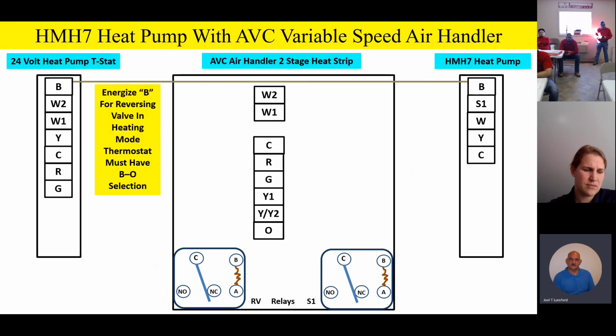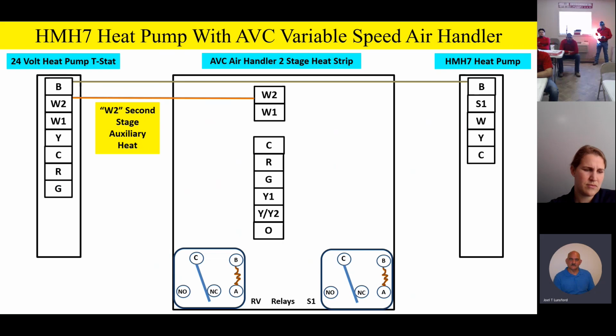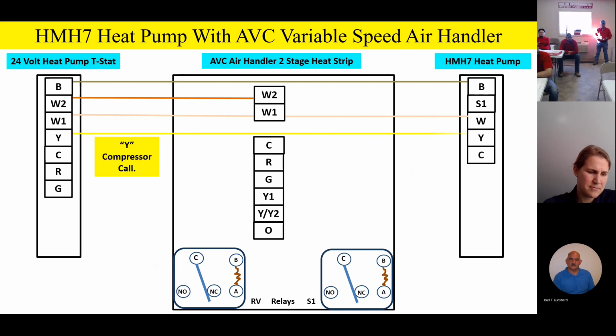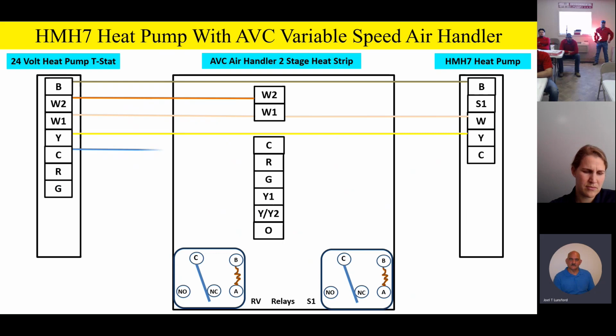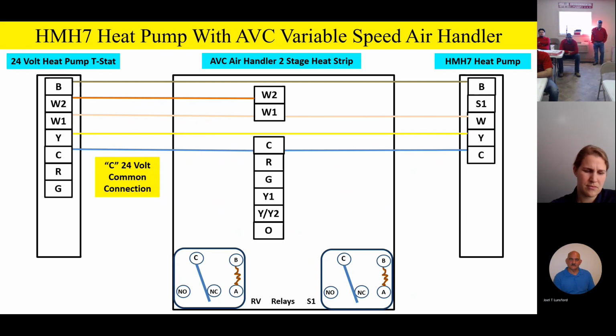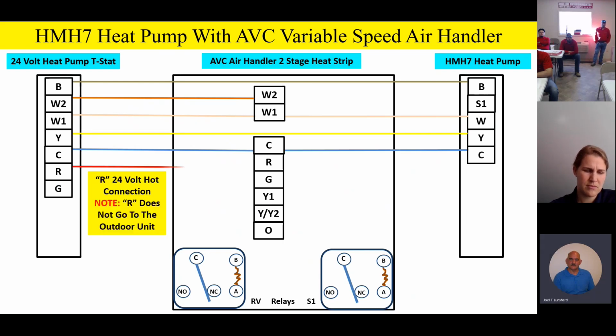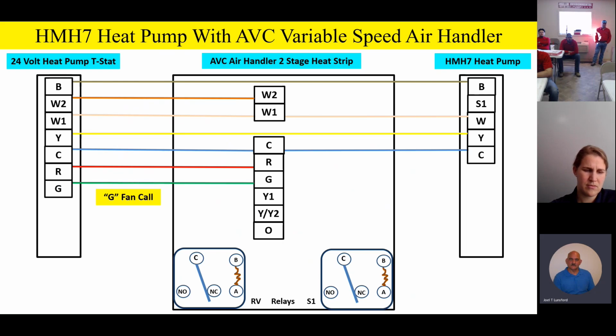Just like we had before, B goes from the thermostat to the outdoor unit. W2 is our second stage auxiliary heat. W1 would be first stage auxiliary heat, and that goes all the way through like we had before. This is looking familiar to you guys. Y is your compressor call. C is 24-volt common. R is your 24-volt hot. G is your fan, just like we had before.